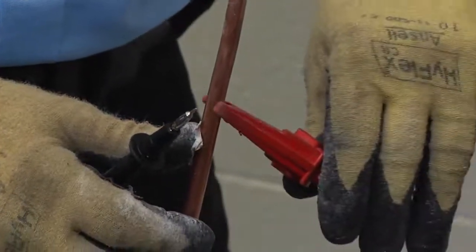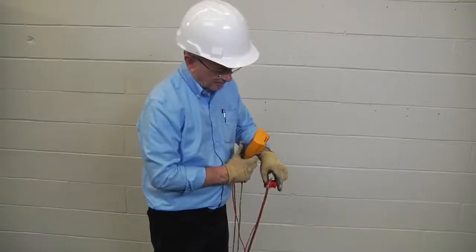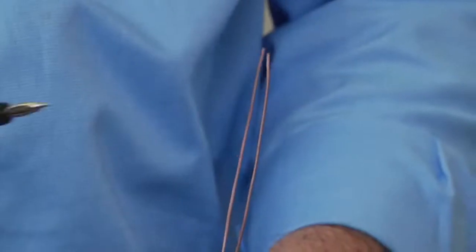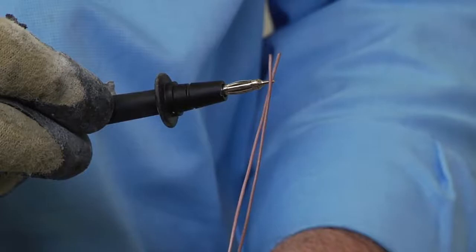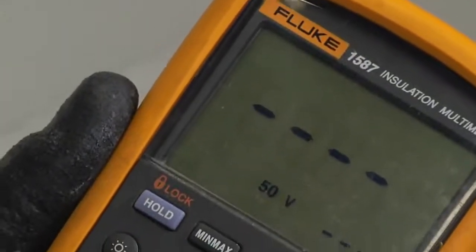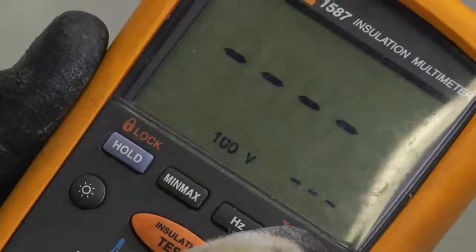Step 2: Connect the positive or earth lead to the cable sheath. Step 3: Connect the negative or line lead to the conductor. Step 4: Turn on the megohmmeter and set the voltage to 500 volts DC.